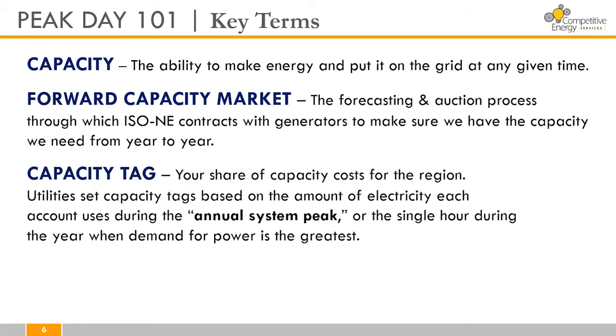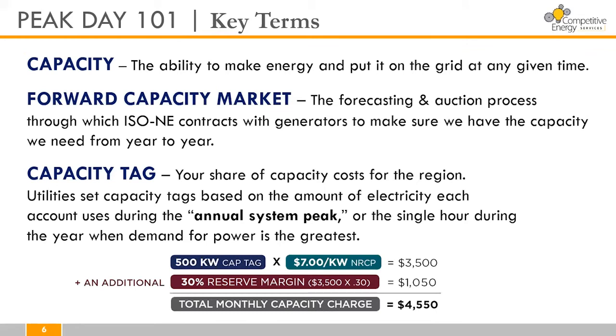So how are your capacity charges determined? You're going to pay for your share of capacity costs based off of the capacity tag for each of your utility accounts. Utilities set the capacity tags based off of the amount of electricity that each account is using during the annual system peak — the single hour in the year when the demand for power is at its greatest. There is a calculation you can use to determine your capacity costs, but if you're interested in learning more we would encourage you to reach out to our team.